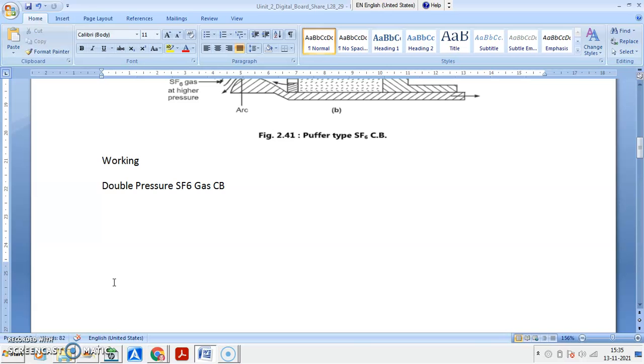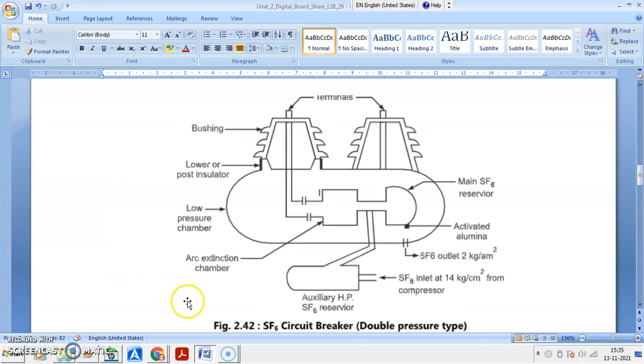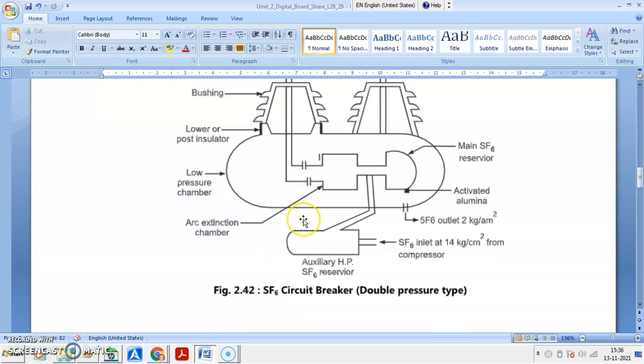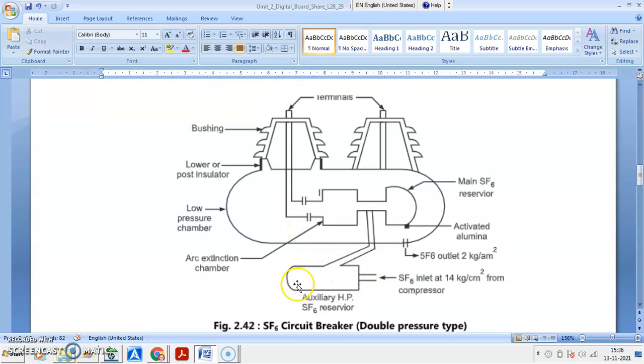In this particular diagram, you can see here you have an auxiliary reservoir, high pressure SF6 gas storage tank, and high pressure SF6 gas is coming to the tank through compressor. Pressure is around 14 kg per centimeter square. So you are having the tank. So this is a bigger assembly than puffer type SF6 gas.